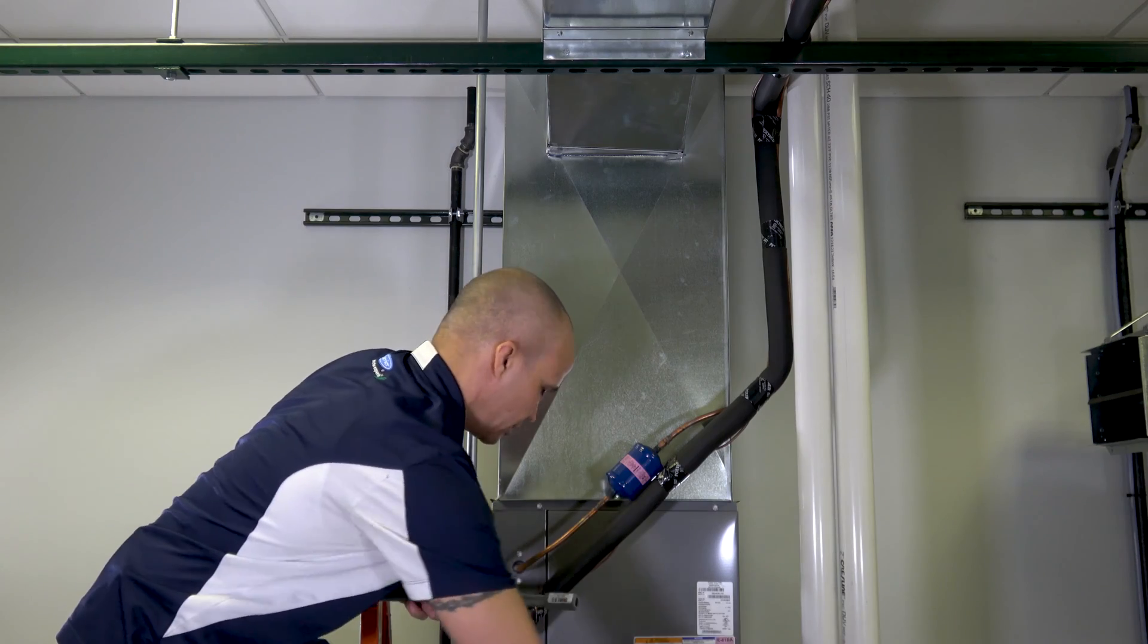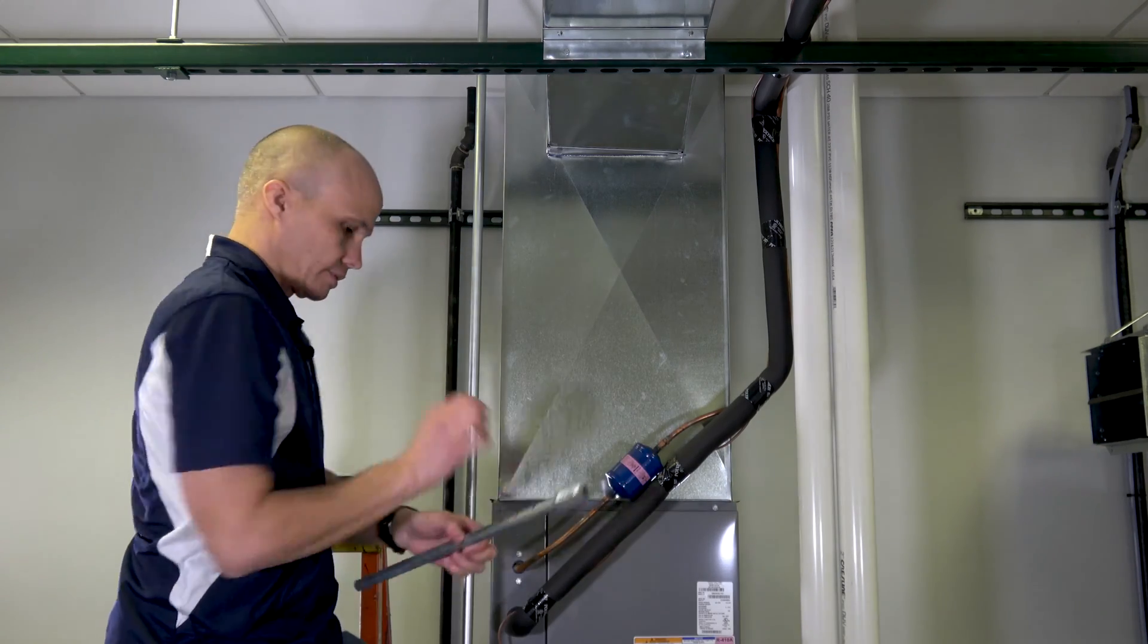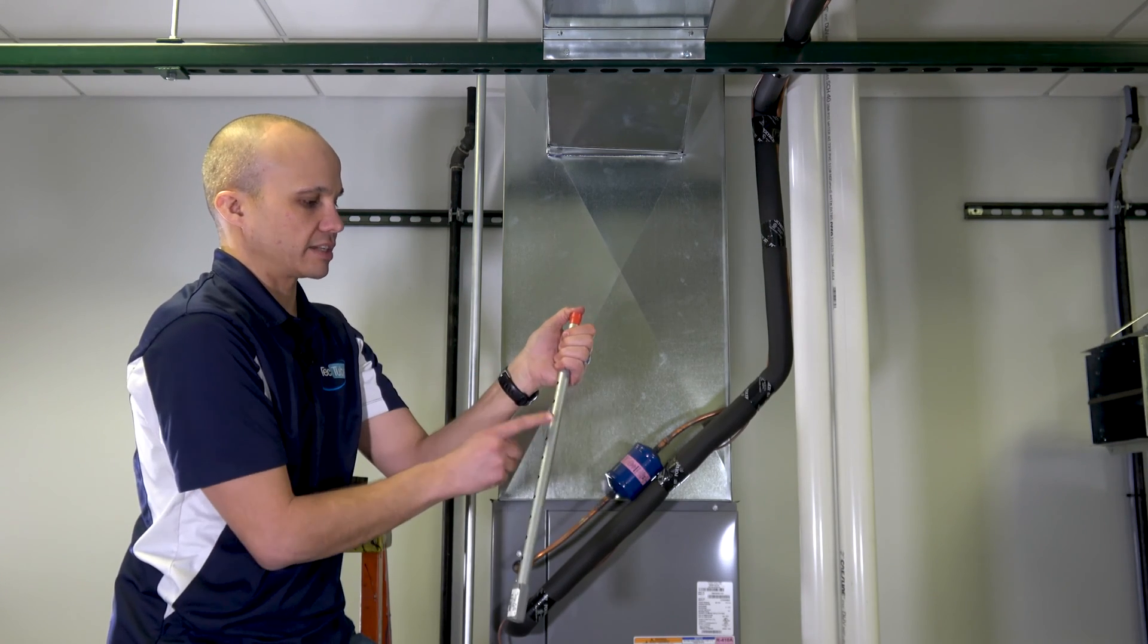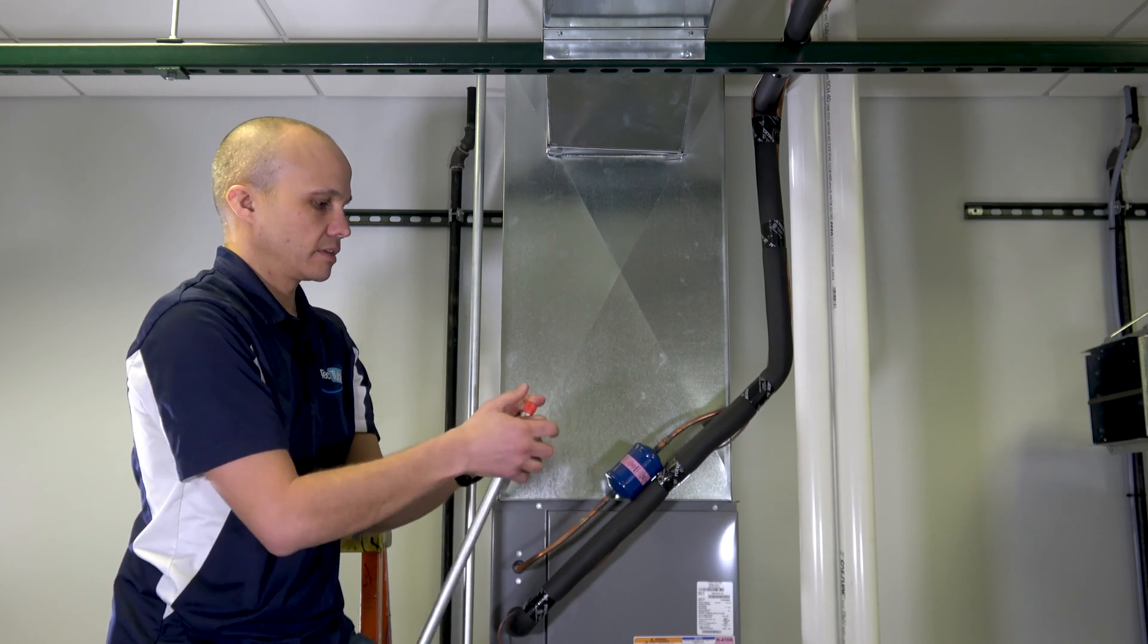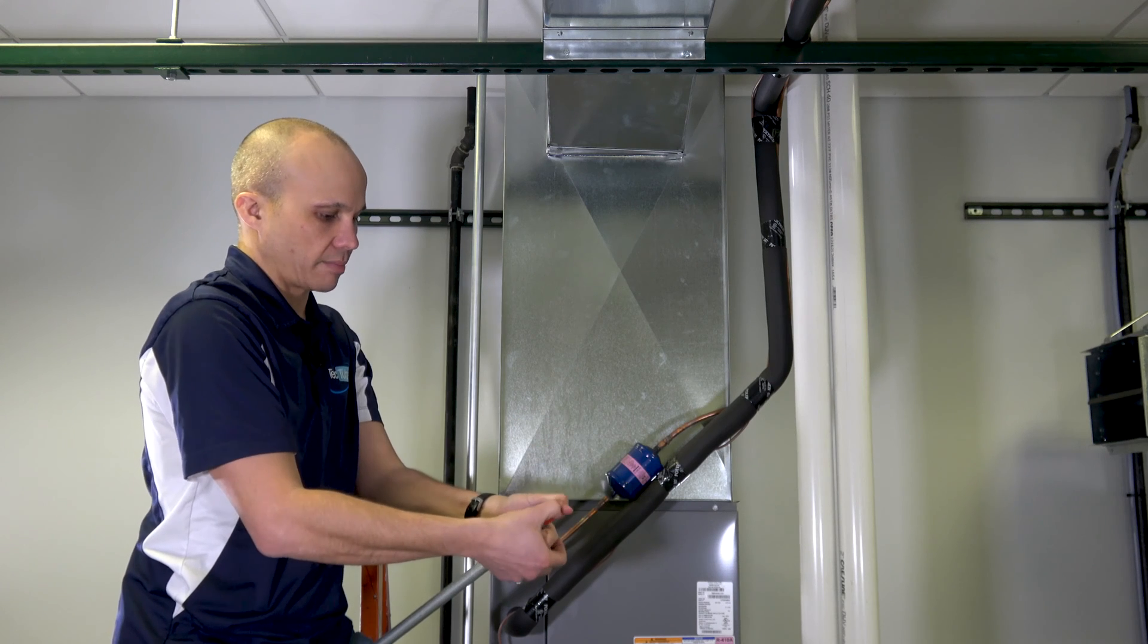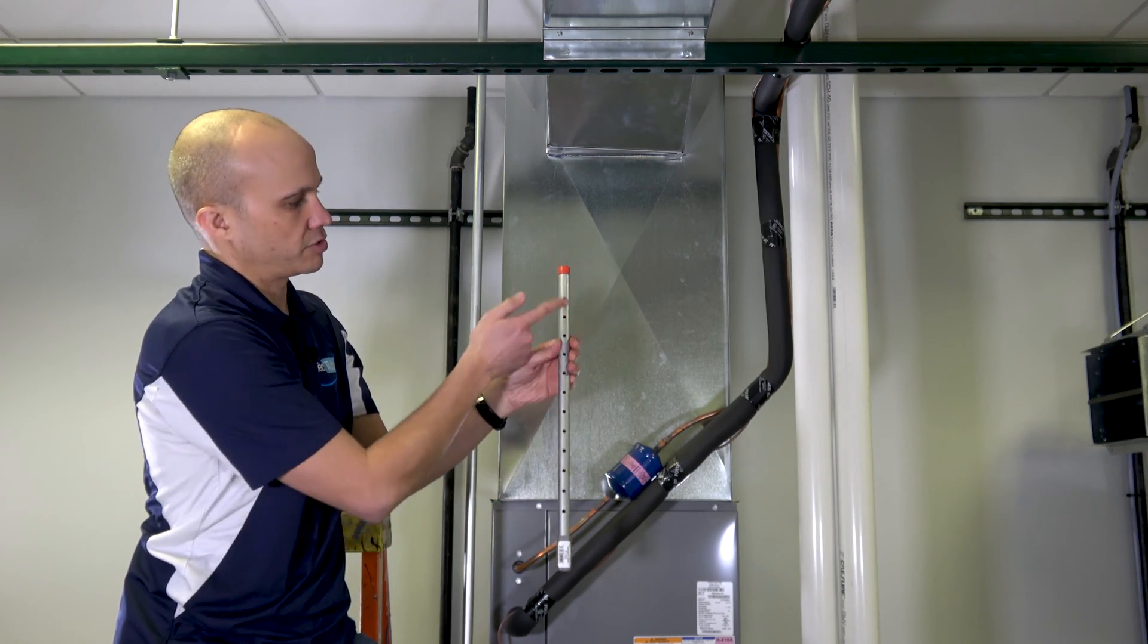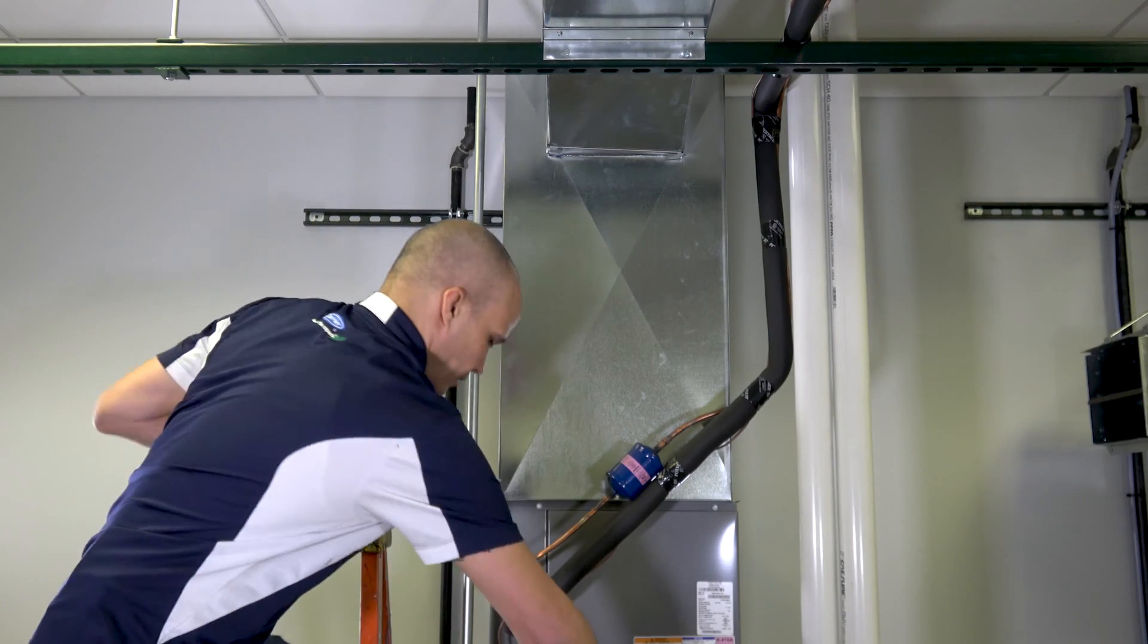The other side of that equation is at the end of this tube I got to put this red cap on here. They ship that separately once again because this tube comes in different lengths. So I got to put this red cap on the end otherwise I'll be sampling too much from the end instead of sampling it at evenly spaced distribution points.